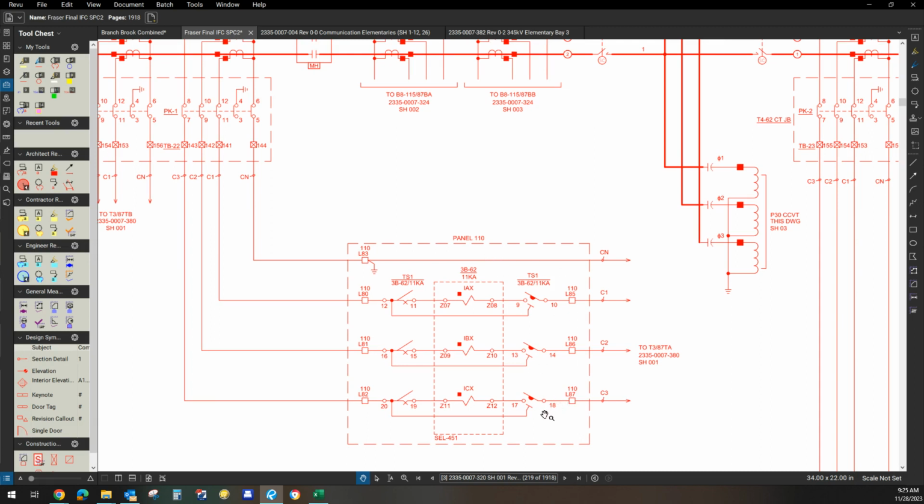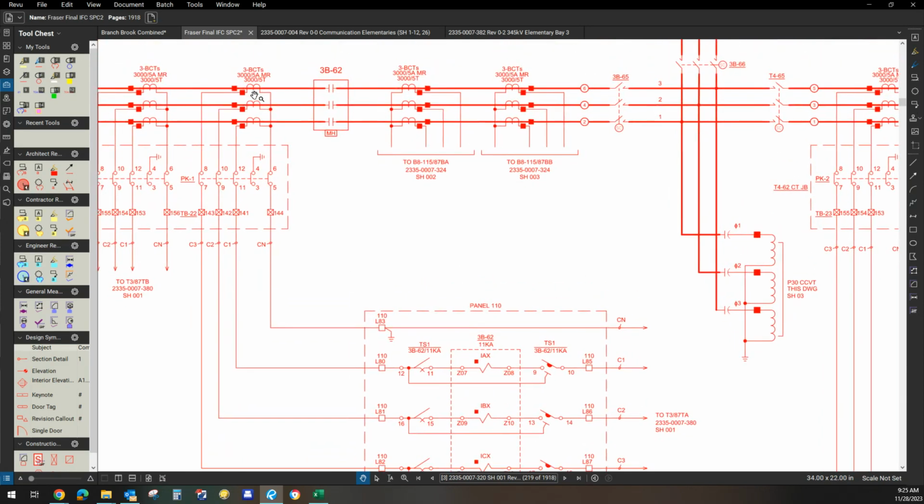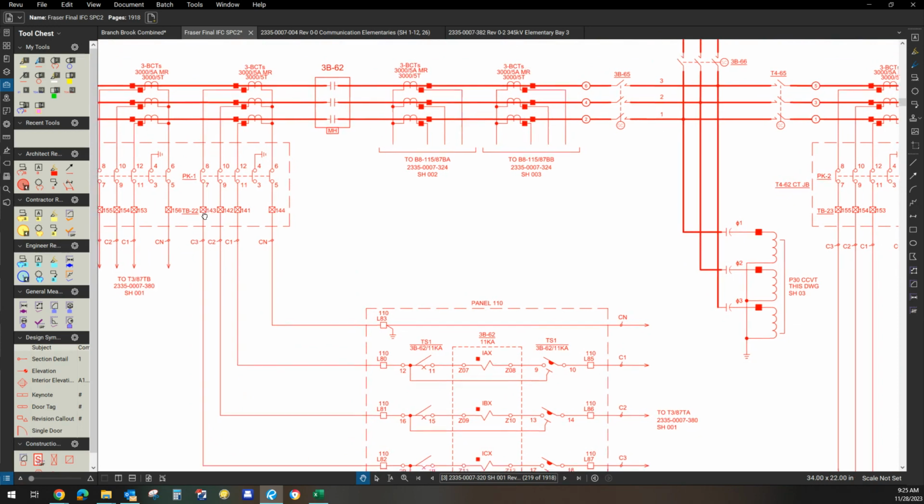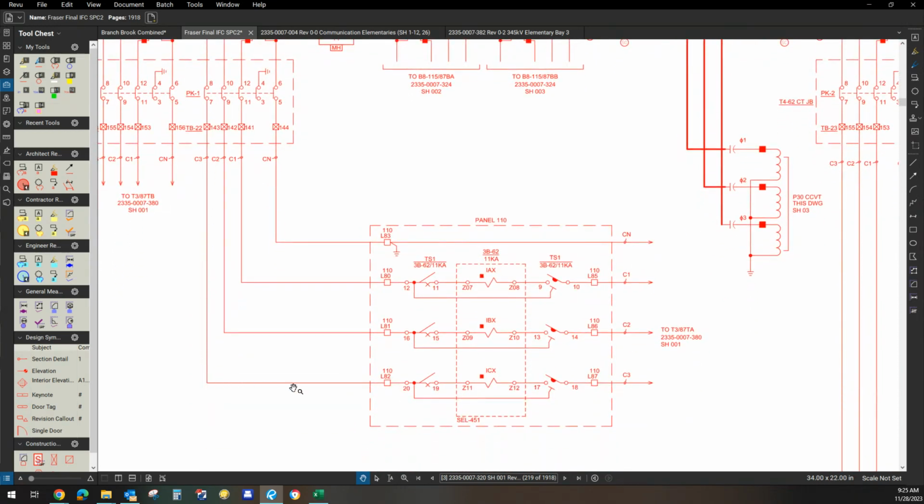Now, all these numbers can be verified on the wiring diagram, but this elementary shows how it needs to be wired and needs to be proved. You need to prove that this path from this CT goes through all these points and into the test finger as drawn, comes out and goes back to the terminal block.